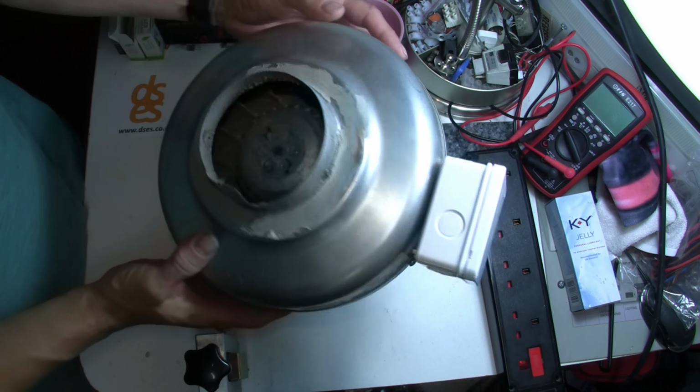We don't recommend anyone installing an item on their own, and all warranties are void if this is the case. All electrics should be carried out by an electrician. You can switch from a neutral to control a fan, and is done this way on a lot of units in other parts of Europe. Well, maybe, but Europe gives less of a shit about polarity and aren't working to BS 7671. Yes, you can physically switch a neutral to control a fan, but why would you think it's a good idea?